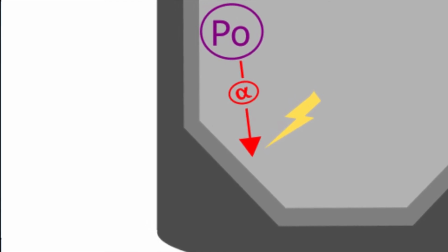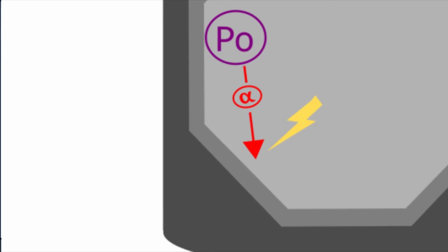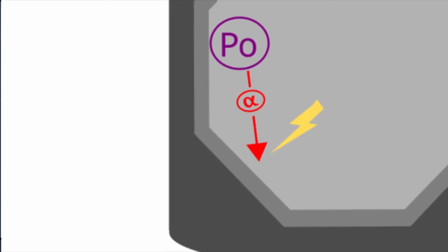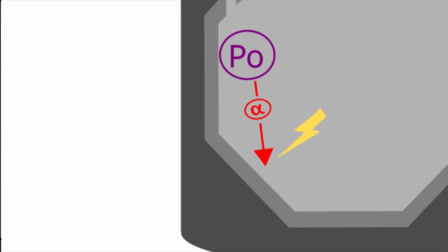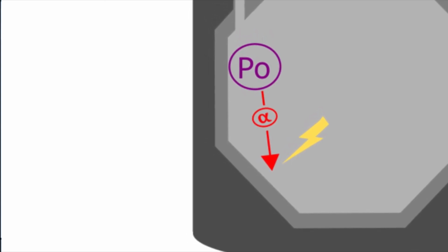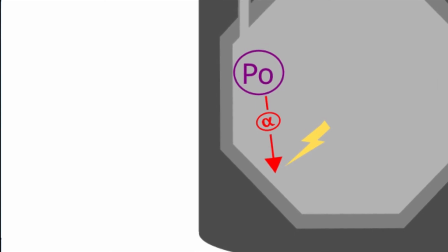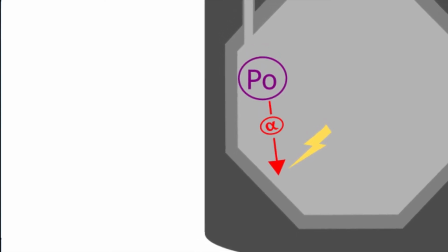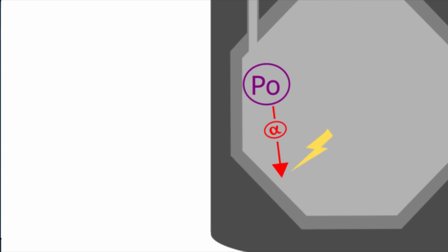The radon sniffer calculates how much radon progeny is stuck in the cell at any time, and can subtract that from the total number of counts. You then get a real-time measurement of the radon concentration in the air being sampled. However, there are some caveats to the previous statement. The calculation only works as long as the sniffer is on.